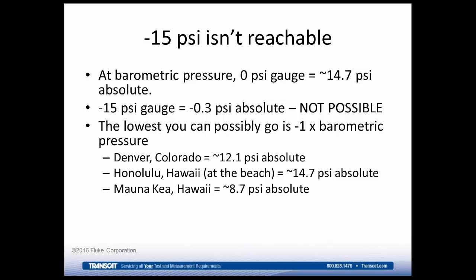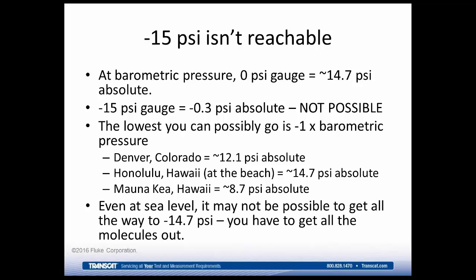So why do we say negative 15? Generally speaking, it's rare for atmospheric pressure to be greater than 15 psi. And in reality, it's more just a rounding situation. You have to be cognizant of your location, your barometric pressure, and seeing what it is. So even at sea level, it may not be possible to get negative 14.7, but at the same time, that's your best case is at sea level.